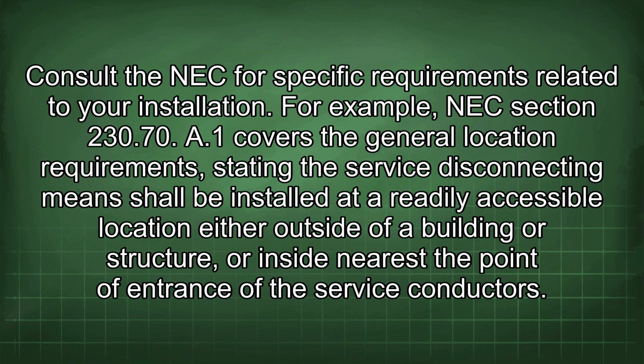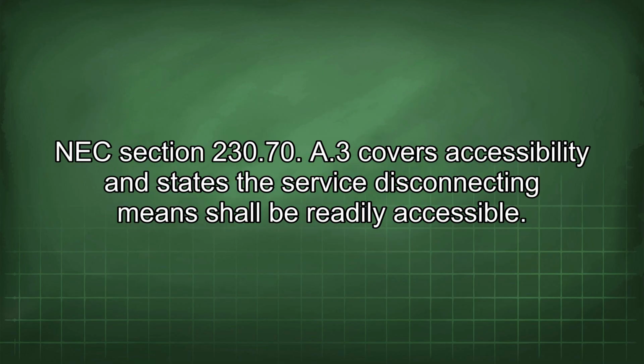For example, NEC Section 230.70(A)(1) covers the general location requirements, stating the service disconnecting means shall be installed at a readily accessible location either outside of a building or structure, or inside nearest a point of entrance of the service conductors. NEC Section 230.70(A)(3) covers accessibility and states the service disconnecting means shall be readily accessible.